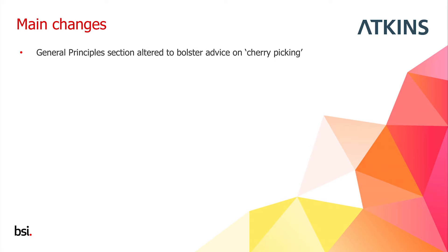The first main change is to the general principles section, which has been altered to bolster advice on cherry-picking. Some designers look at all the codes and standards available, pick the most palatable bits from each, and present that mishmash to building control as a fire-safe design. That doesn't work — BS9999 is a comprehensive standard where certain parts rely on other parts to be safe. Mixing palatable bits of BS9999 with palatable bits of Approved Document B may not produce an acceptably fire-safe design.